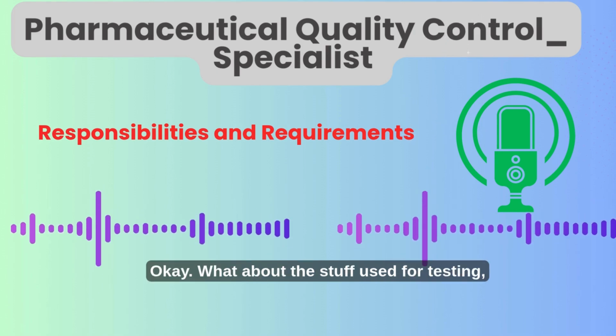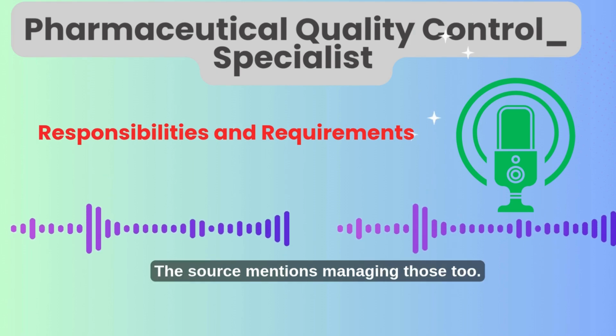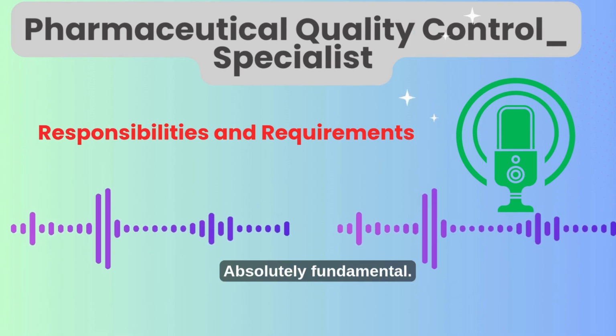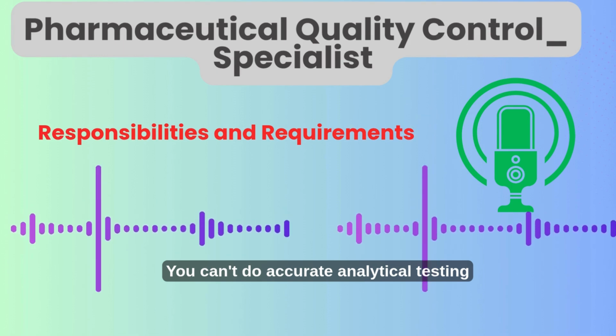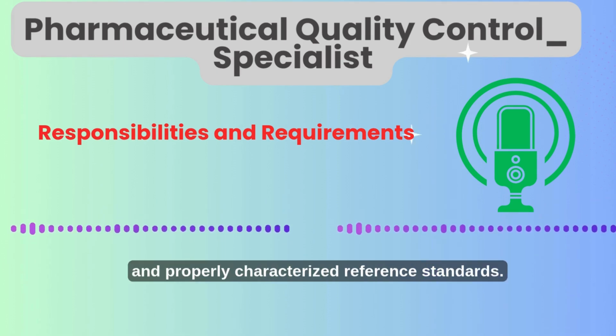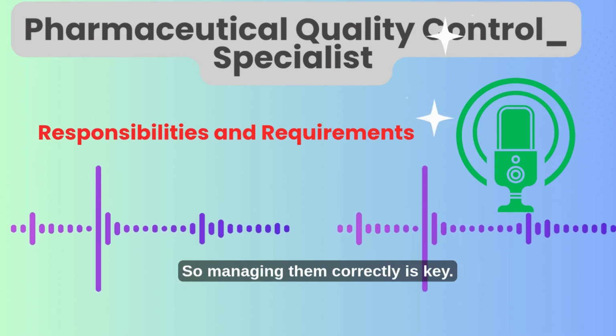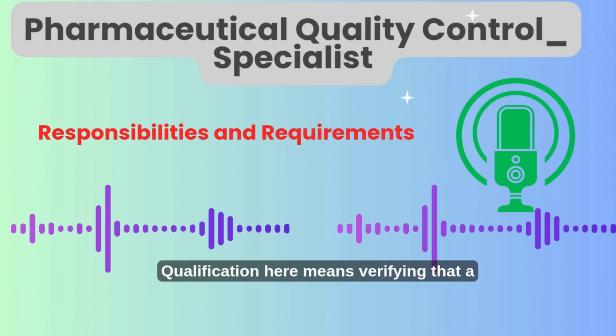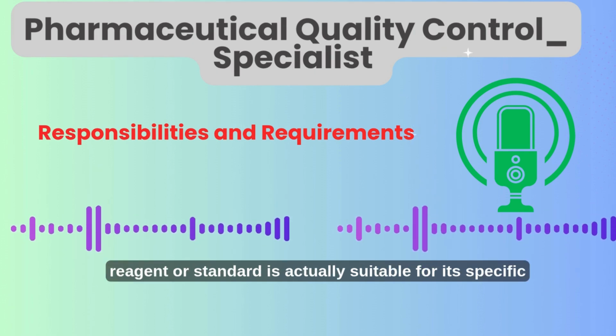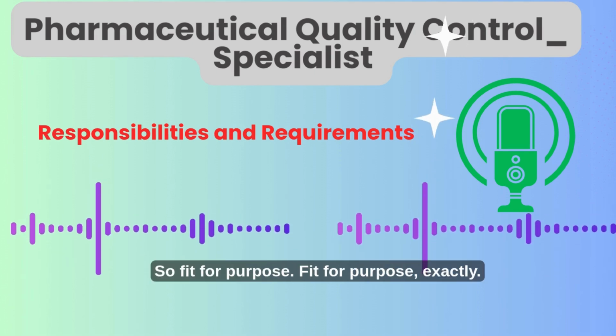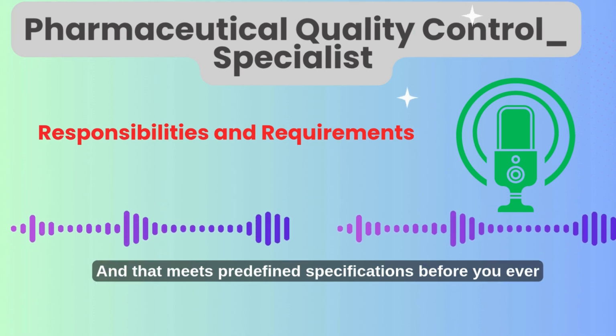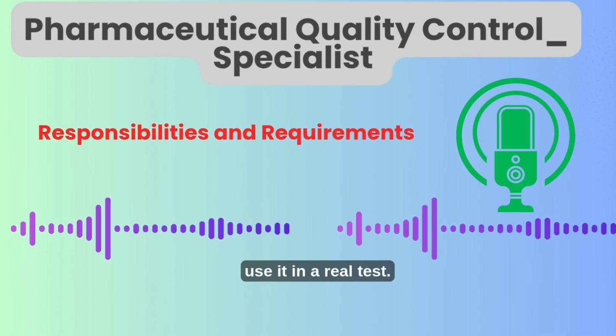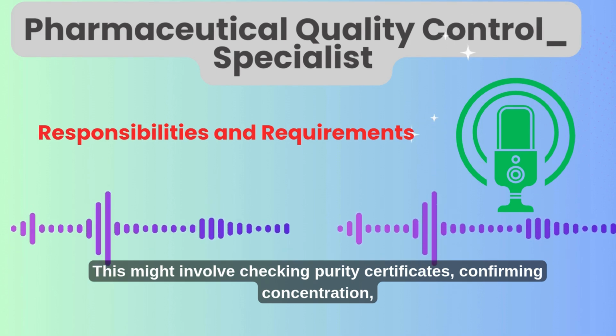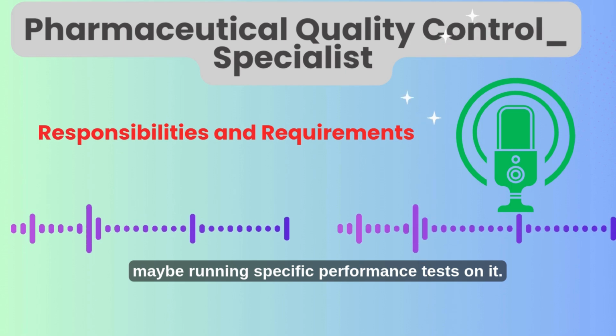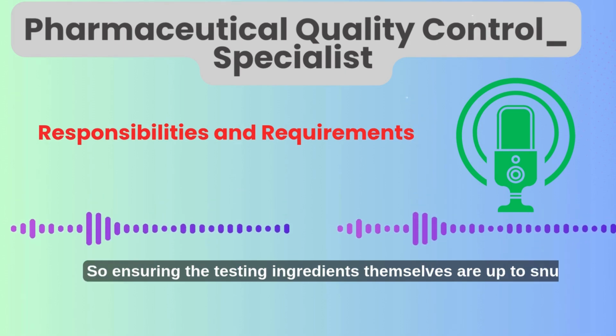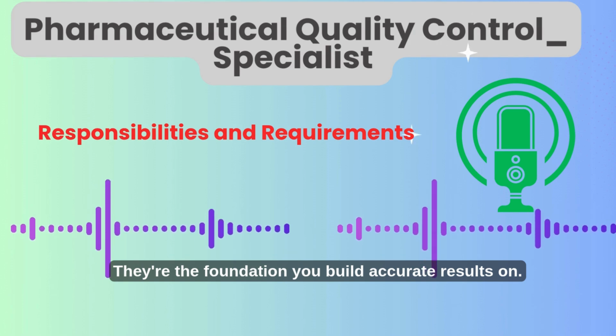Okay, what about the stuff used for testing, reagents and standards? The source mentions managing those too. Absolutely fundamental. You can't do accurate analytical testing without high-quality reagents and properly characterized reference standards, so managing them correctly is key. Qualification here means verifying that a reagent or standard is actually suitable for its specific analytical job. So, fit for purpose. Yeah, exactly. And that it meets predefined specifications before you ever use it in a real test. This might involve checking purity certificates, confirming concentration, maybe running specific performance tests on it. So ensuring the testing ingredients themselves are up to snuff. Precisely. They're the foundation you build accurate results on.